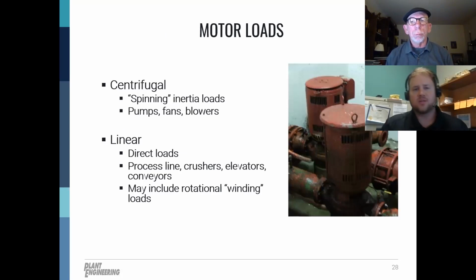So last couple of things here on motor applications and some maintenance techniques. Here we have a few examples of motor loads, and then after the loads, we're going to move into the power quality topic. Generally, there are two types of loads. You've got centrifugal and linear. So centrifugal includes spinning inertia loads, where the load will tend to increase with speed. Some examples of centrifugal loads are pumps, fans, blowers, and such. The linear loads will be more direct loads. So crushers, elevators, conveyors, and typically linear loads are constant torque applications. So independent of speed, they really need the same amount of torque.